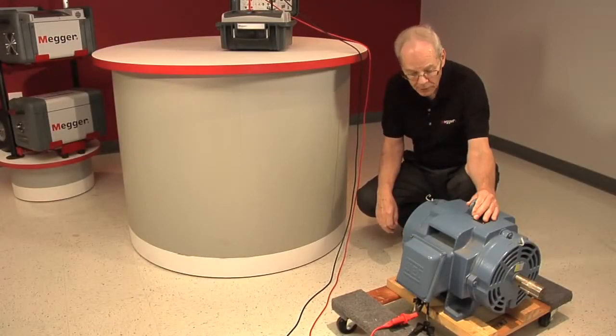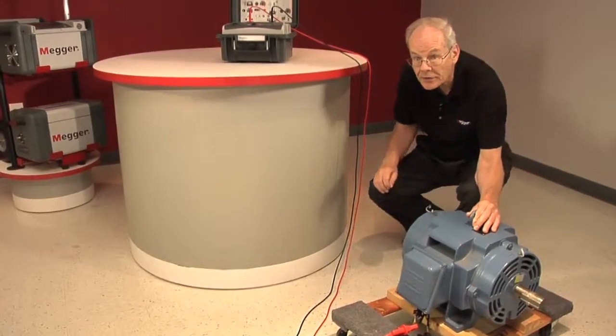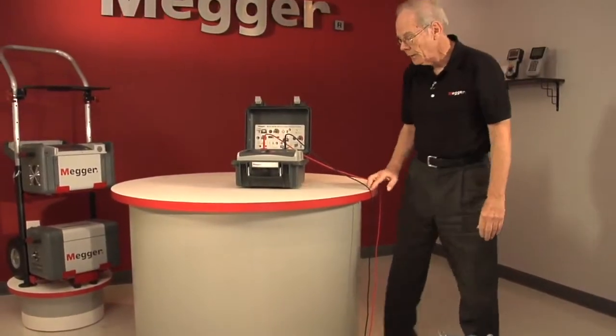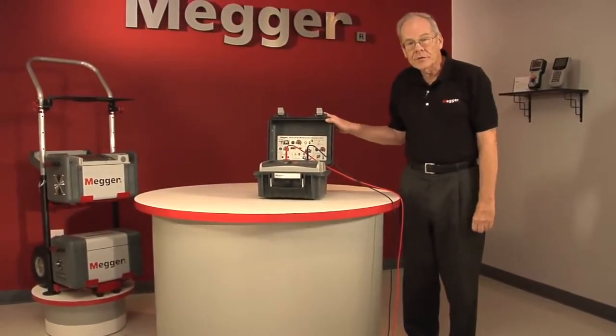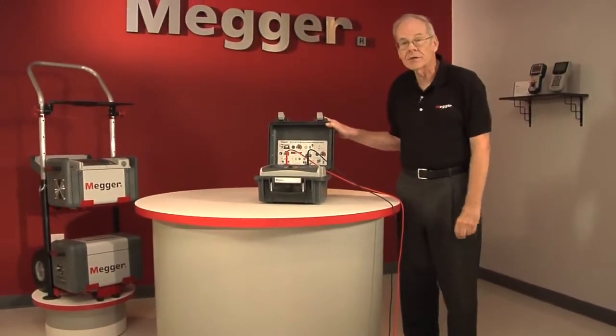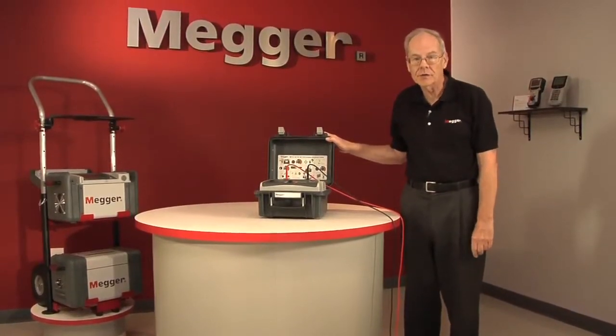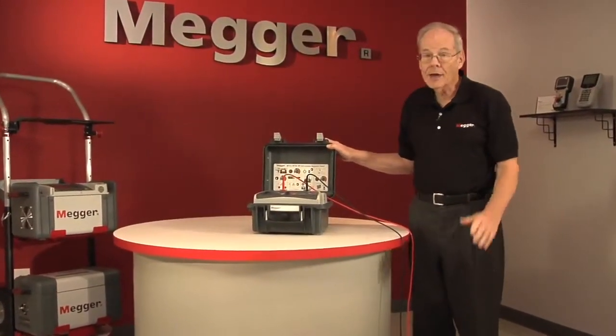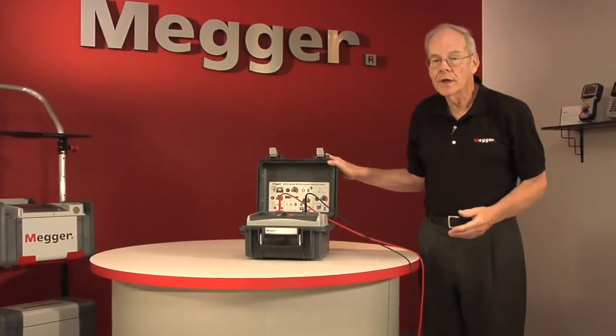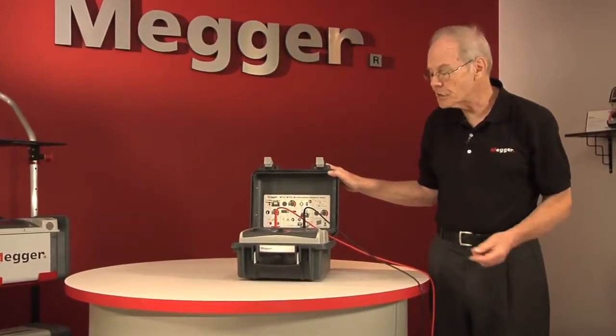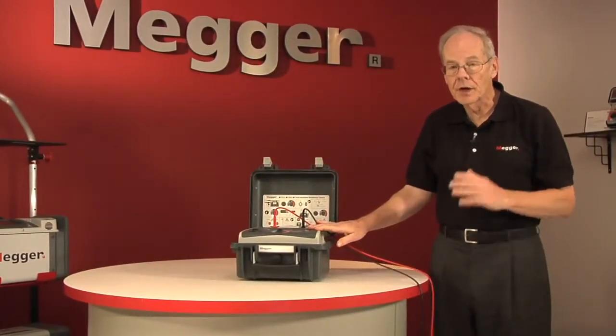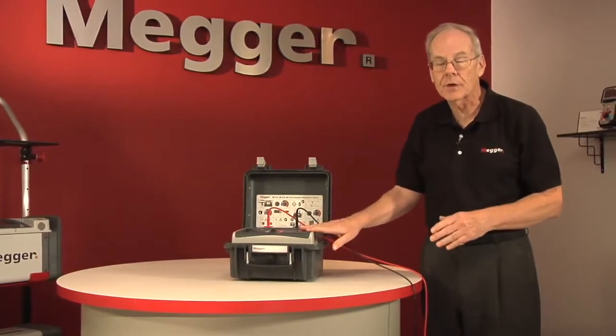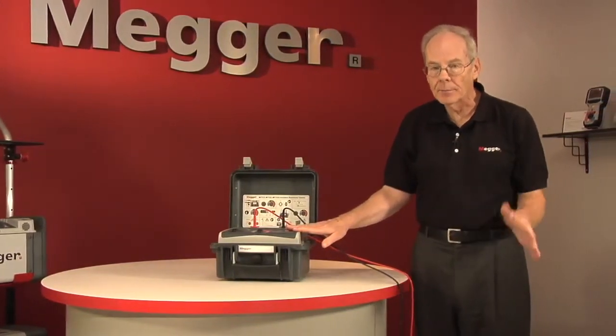Here in the laboratory, we've connected to an isolated test motor. And we're going to test it with the Megger MIT 1025 10kV insulation tester. Now, in actual practice, you would observe industry standard safety practices. The tester itself is redundantly designed for safety, but the test item can be dangerous.